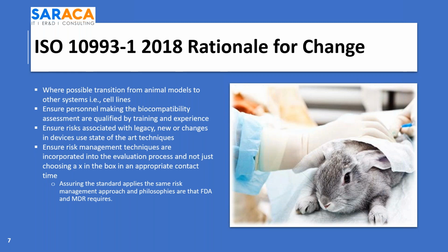There is a general feeling that risk management has not done well because we're still having recalls. We've had a series of recalls this month, which are phenomenal. There are things that should have been considered, batteries dying, connections becoming loose, and so forth. That says that these risks were either not considered during the development process, or the essential performance of the device was not adequately tested.